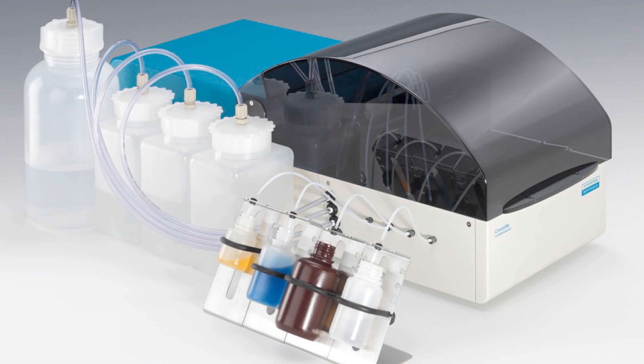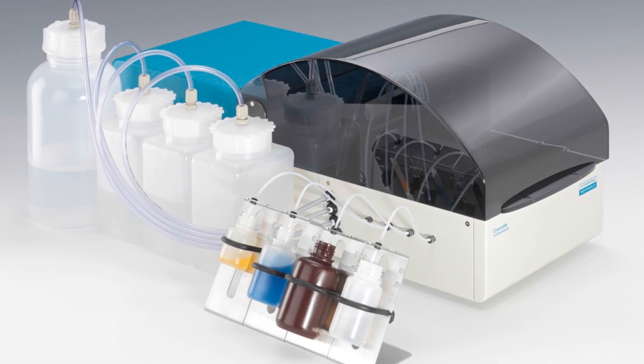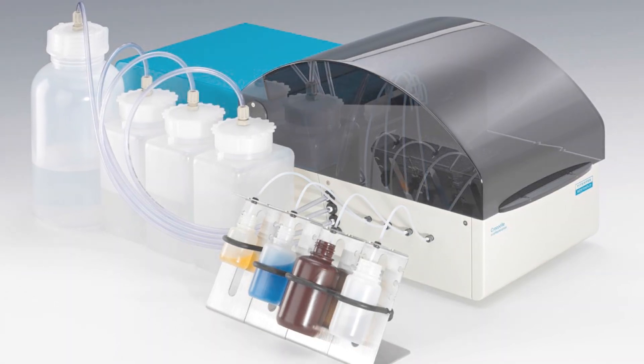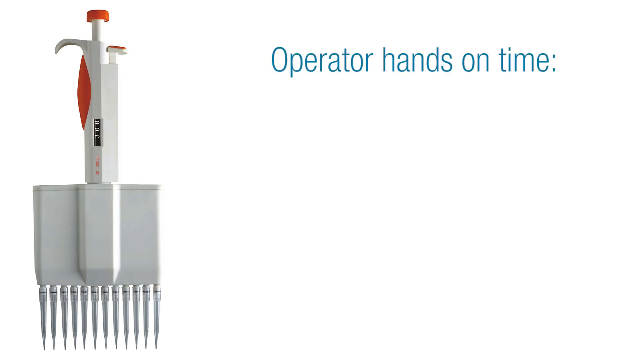In summary, total assay time for the automated assays are approximately the same as when the assays are performed manually, but after having the plate prepared, operator hands-on time is reduced from 110 minutes to approximately 15 minutes.